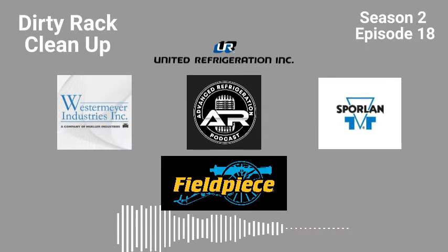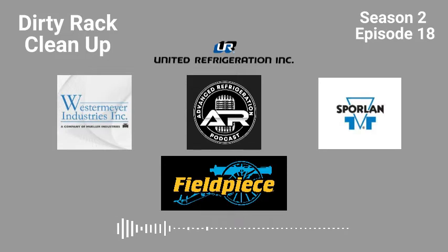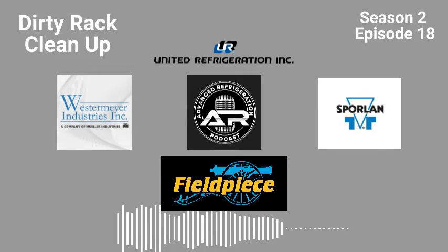Go ahead, Brett. So two things. If you have a hot gas defrost or cool gas defrost, are you doing anything to the discharge line? Like if you continually have blocked filters on your strainers on your TXVs, I've seen where people have put a dryer shell on the discharge line of that gas going over there, to basically prevent any of that bypassing, because if you're coming right off the discharge, you're not being filtered by the liquid. Yeah, you're being filtered by the suction a little bit, but you're potentially moving all that stuff around.